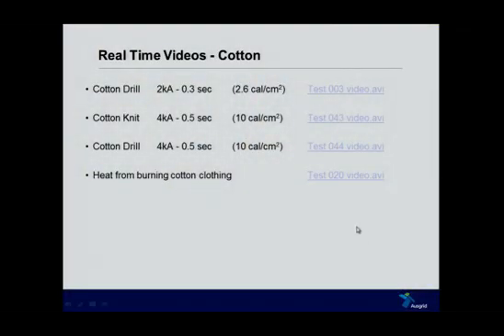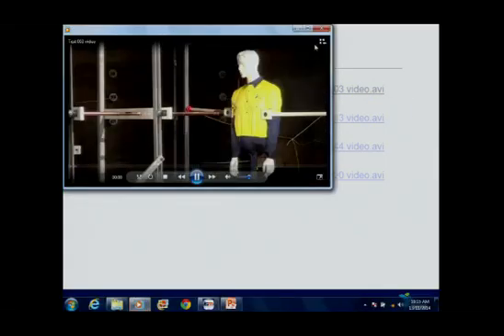So enough about me flapping on about plasma, let's look at some stuff blowing up. It didn't take us a lot of energy or time to get a reasonable amount of energy at the mannequin. You've seen this first test, a fault current of 2 kA for an arc duration of 0.3 of a second, giving an average measured energy of 2.6 calories.